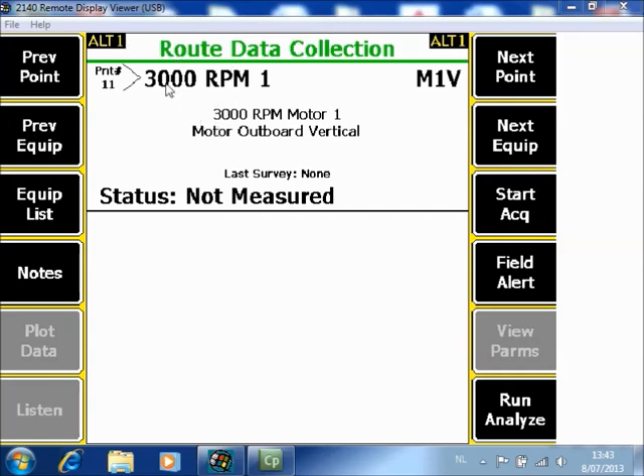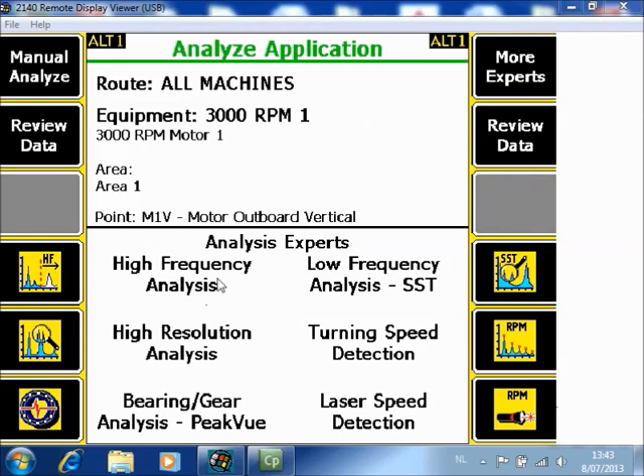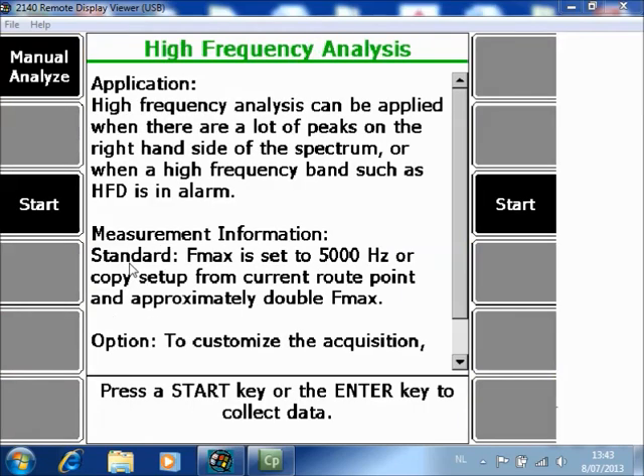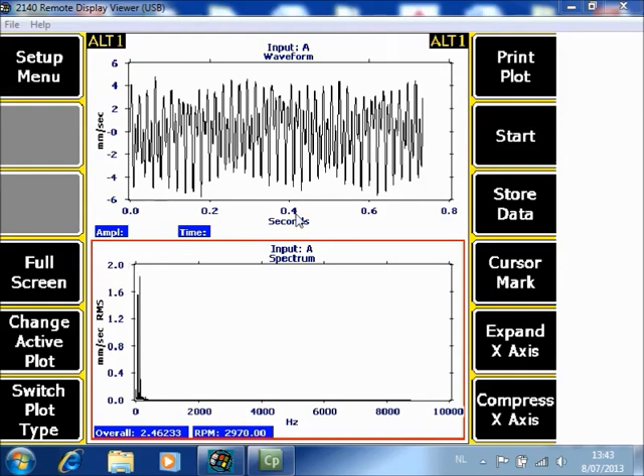On purpose, the next machine has a speed that is double the previous machine, so the Fmax in the Route mode will already be more or less double. Let's take a look — we first collect the regular route data by pushing F9 to start acquisition. A spectrum roughly up to 3500 Hz is measured. When you go to F12 Run Analyze and start a high frequency analysis by pushing F4, an additional spectrum is measured up to roughly 8000 Hz — the double frequency. This data can now be stored in the Route mode by clicking F9 store data.